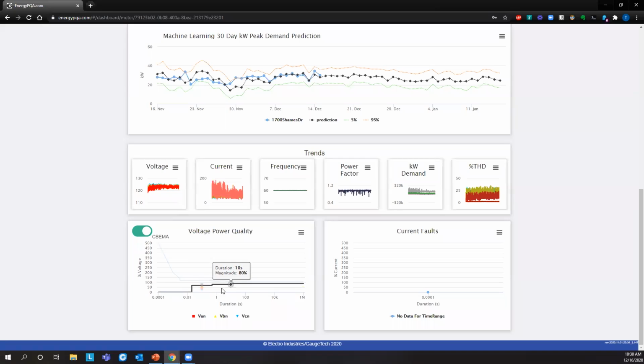Anything that happens below this black line are events that probably won't damage your equipment, but they may cause your equipment to shut down. So if you have a server that takes 30 minutes to an hour to start back up again, even though this is not an equipment failure issue, this is a loss of revenue because now you can't operate for the next 30 minutes to an hour while that machine is starting back up again. Anything that happens up here are voltage surges, which could potentially fry the power supplies of pieces of equipment on your system.